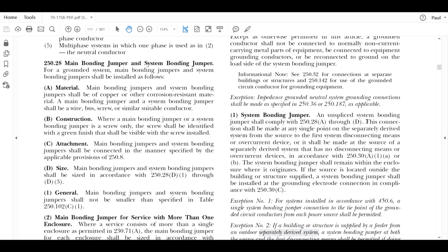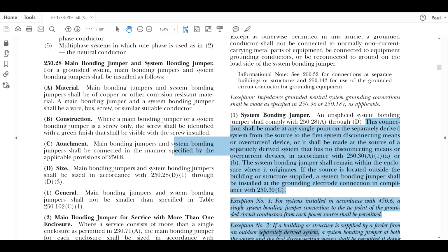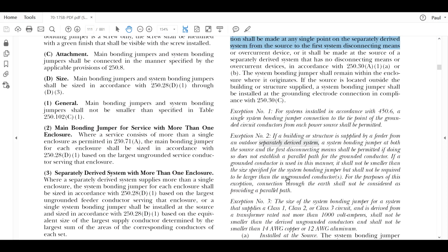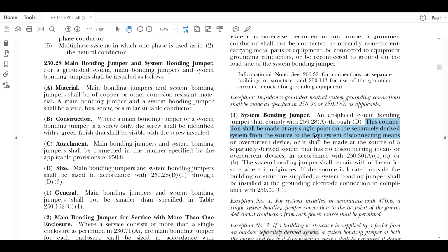It also says that this system bonding jumper connection shall be made at any single point in the separately derived system from the source to the first system disconnecting means. So it could be in the transformer or it could be in the first disconnecting means. Typically not to be installed in both. It can be if there's no parallel path for the grounded conductor, and that's under exception number 2. But in reality, most people choose one or the other. Most people are going to put it in the transformer rather than in the first disconnecting means. Okay, but anyway, there you go.